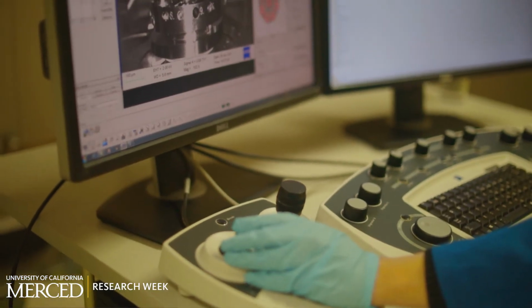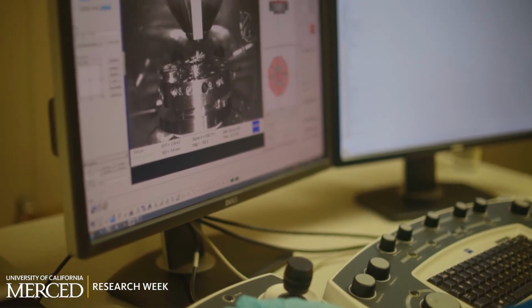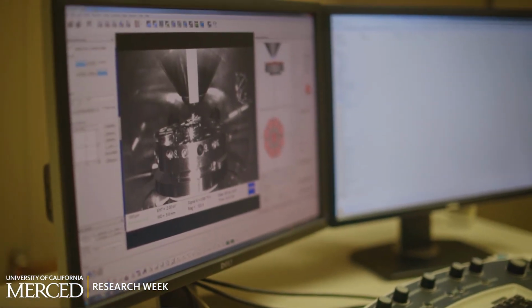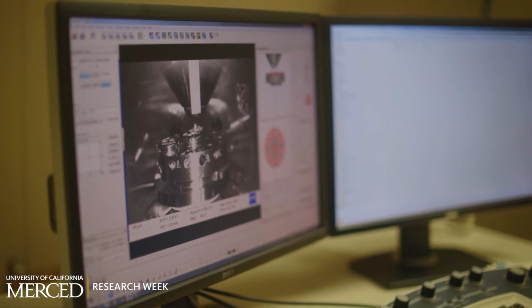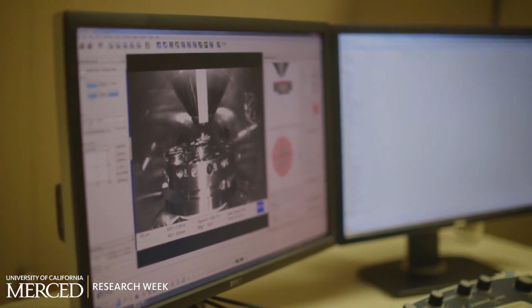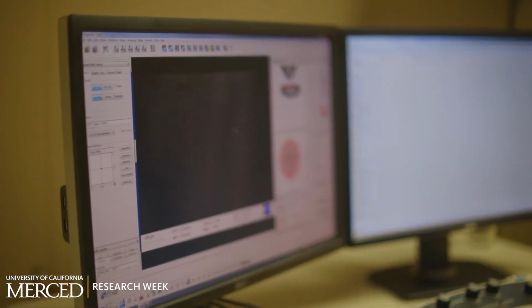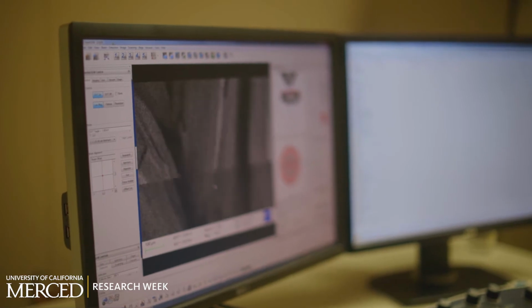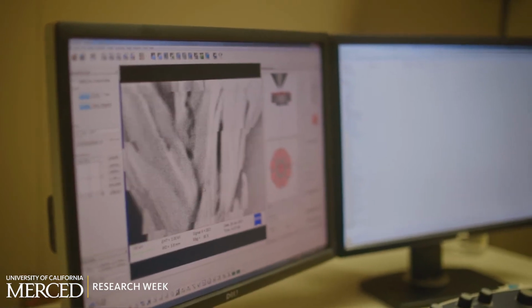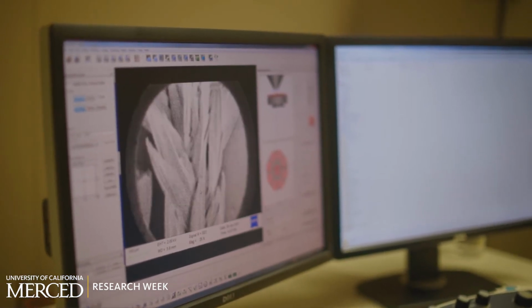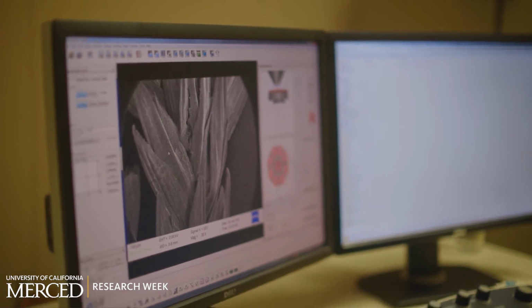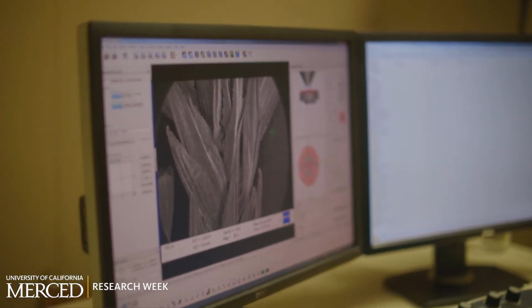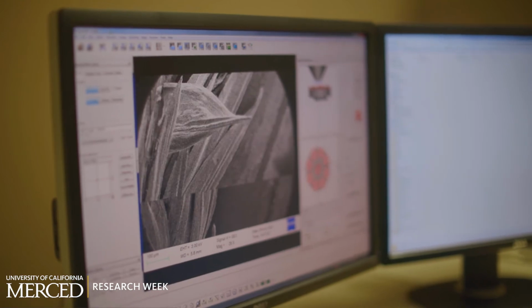Okay, so we already have our sample inside the sample chamber here. Earlier we had to vent the chamber. Since it's always in vacuum, we put the sample in and then pump the chamber. So now that it's already pumped, we have stage controls here, moving up the sample. You can see our sample here. And we're moving it close enough so we get higher resolution imaging, depending on the working distance here.